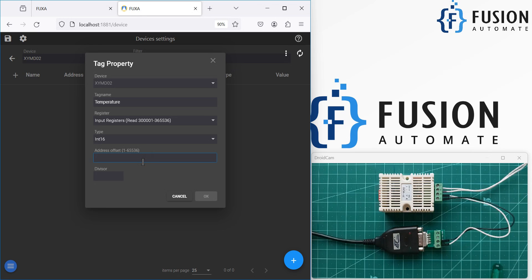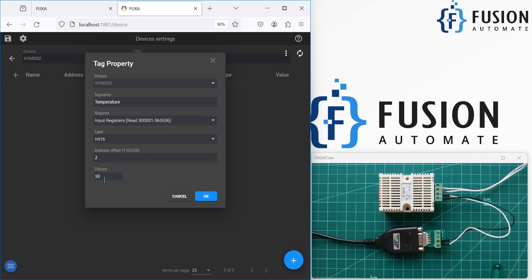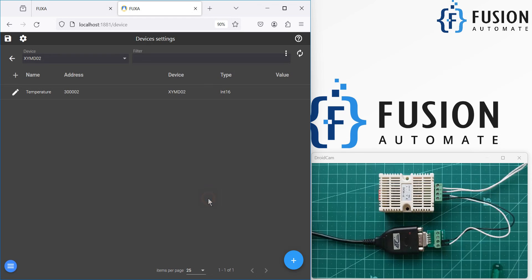For the address, you don't have to write 300003 or 300002 — you just have to write the offset value. We are reading data from the second Input Register, so we write 2 here, because the device provides temperature data on Input Register 2. We want to divide the raw value by 10, so we will set the divisor to 10. That's it — we press OK.